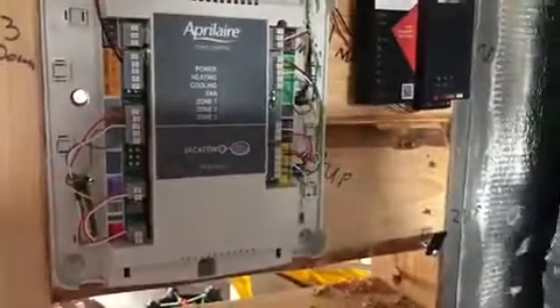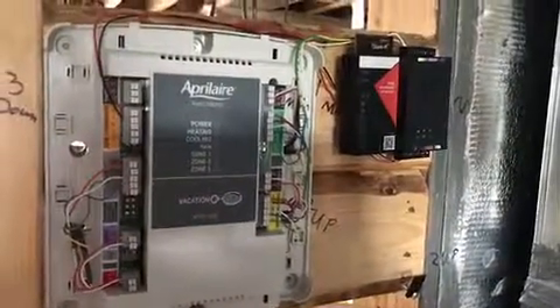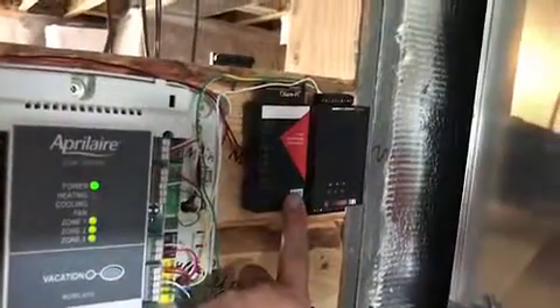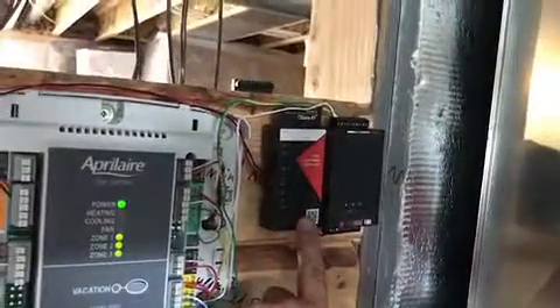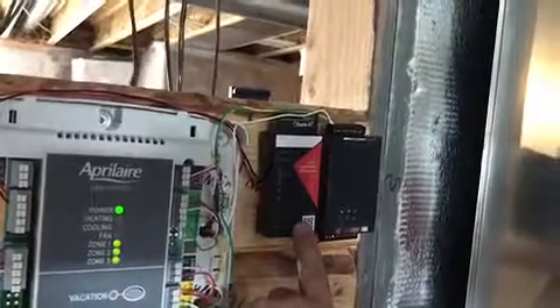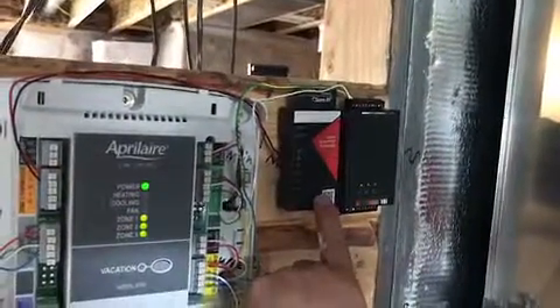And then we've got the control wires. The call for heat, call for cool, call for fan right here, coming down and connecting into the Zone 2 thermostat on the Aprilaire zone controller. So we've got both sides now connected. I'm going to do the test button to show what kind of signal we get up through 3 levels of the house.